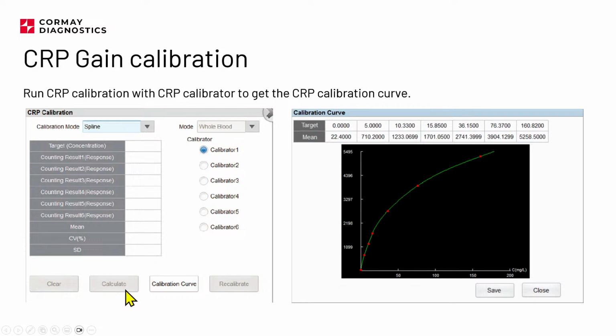this calculate button will be active. So you need to press it, and the analyzer will calculate, or make, a new calibration curve. And calibration curve is the button which shows you the previous one or the new one if you want to see it. Recalibrate is basically a button which erases the previous data, right? Recalibrate. So please make sure that you are not using it when you don't want to delete the data, right?